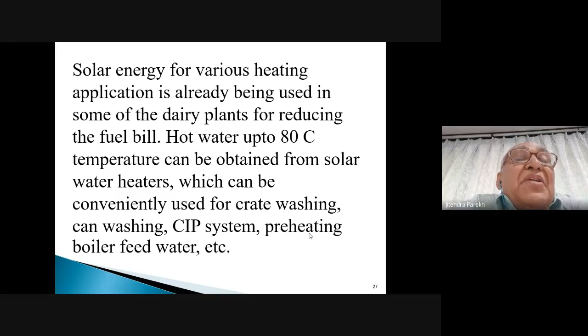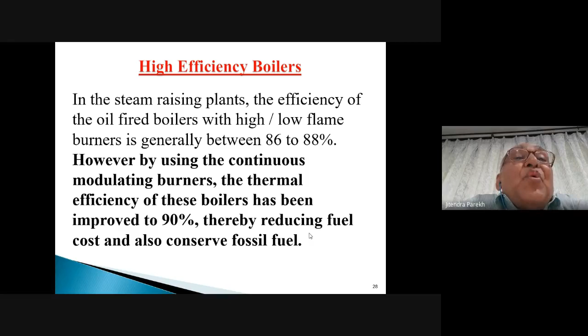Now we are talking about high efficiency boilers, which are generally available in India. We get an efficiency of about 86 to 88%. However, by using continuous modulating burners, the thermal efficiency of this boiler has been improved to 90%, thereby reducing the fuel cost and also conserving the fuel. So basically, we are talking about utilizing continuous modulating burner systems in the boilers, which will improve the efficiency of the boiler up to 90%.